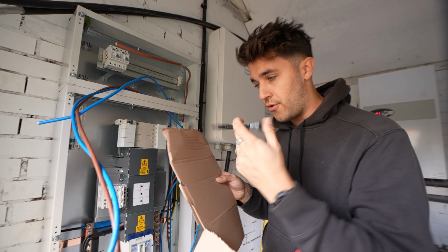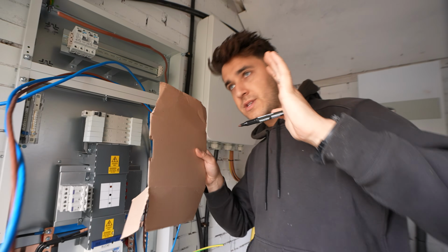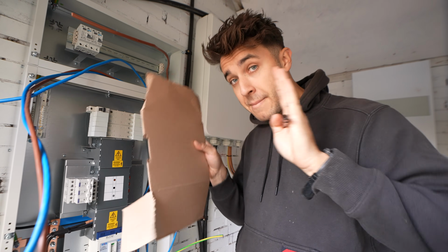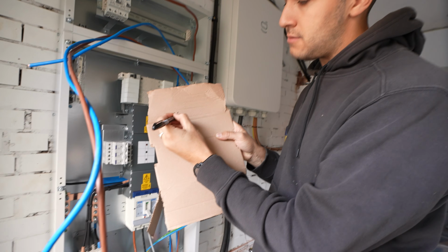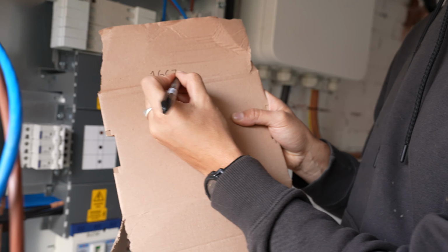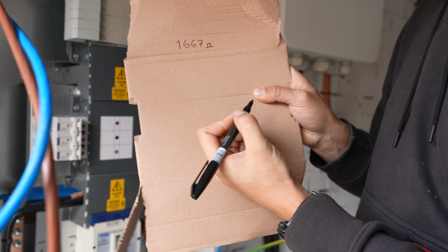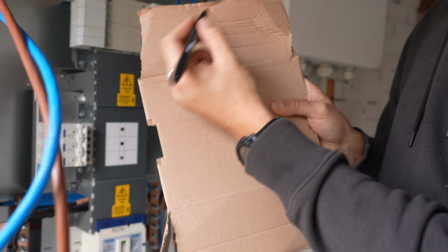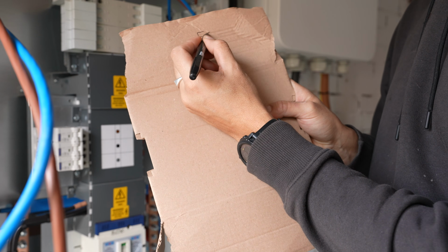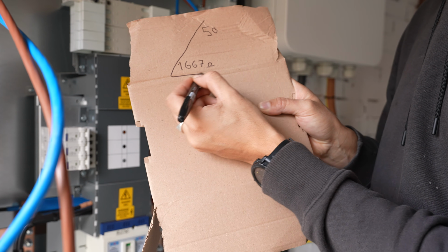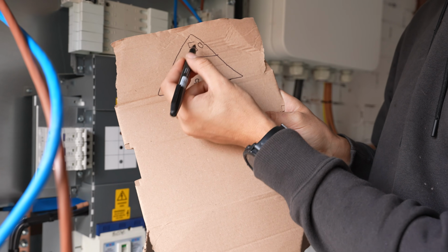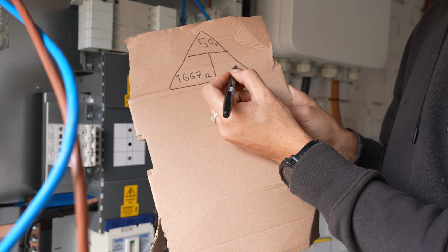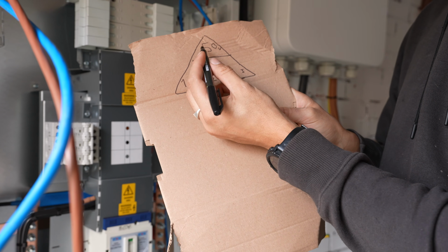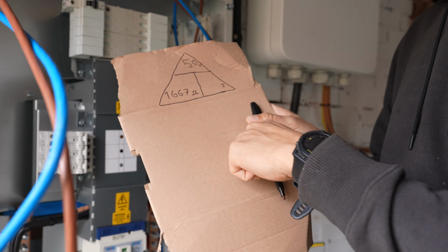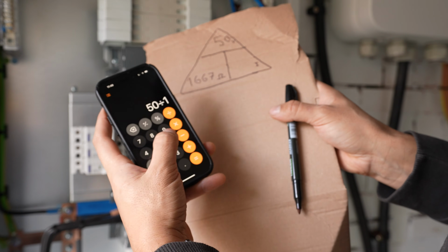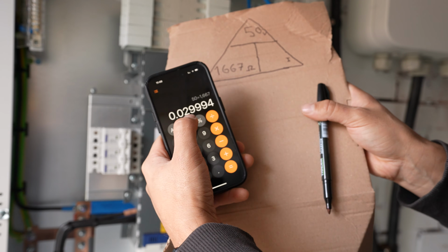I know technically we say 100 ohms or we say 200 ohms or whatever, but the actual maximum allowable is this magic number here, 1667 ohms. So if we know that reading and we know that our voltage has got to be 50 volts, remember the Ohm's law triangle? If we're trying to achieve that, to get our current, all we need to do is divide that by that. If we do 50 divided by 1667, 30 milliamps, give or take.